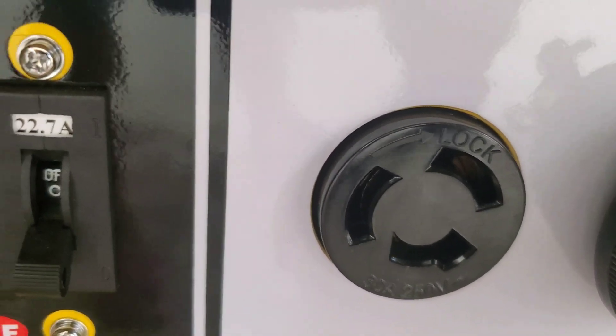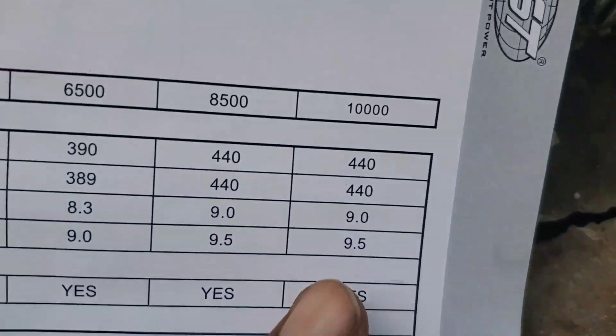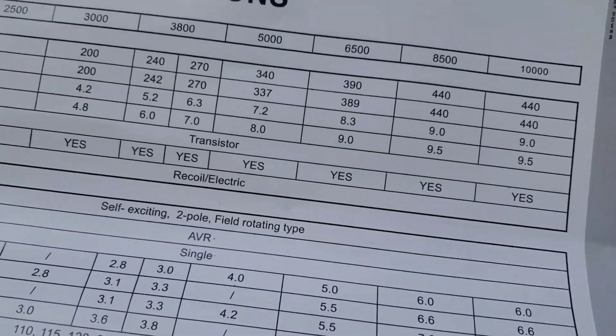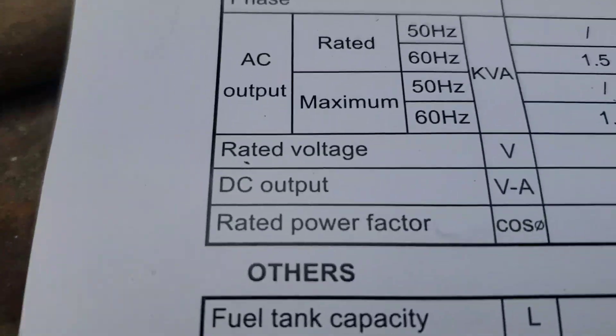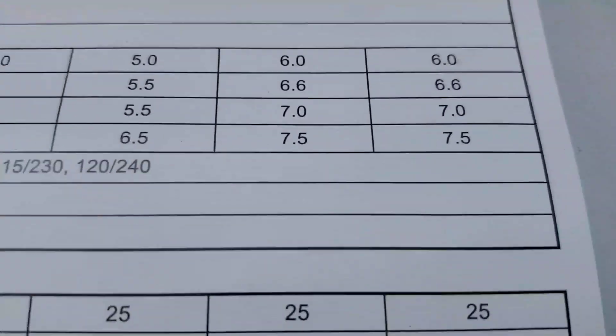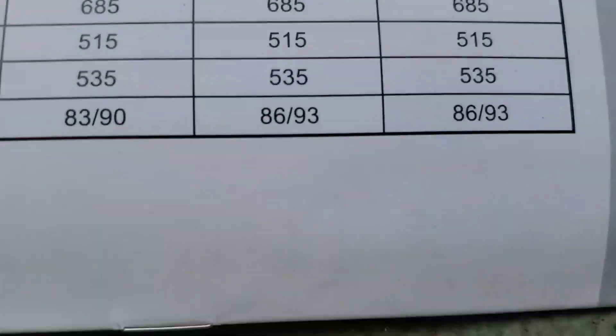This outlet here is rated at 30 amps — 30 amps times 250 volts — though we know we're not going to output 250 volts, so this is limited to 220 volts at about 6,900 watts. Looking at the manual models, the biggest they show is the 10, with a 9.5 horsepower engine — that's not our model, but it's the manual they gave us. Maximum at 50 Hz is 7 kilowatts. Our voltage is 220 volts. The weight is 86 kg — that is heavy.